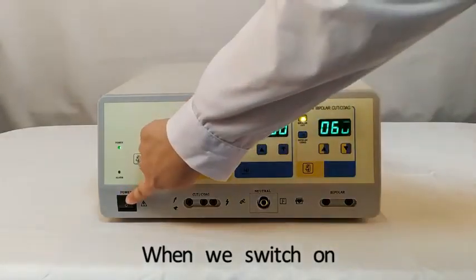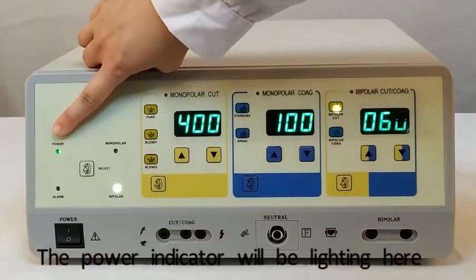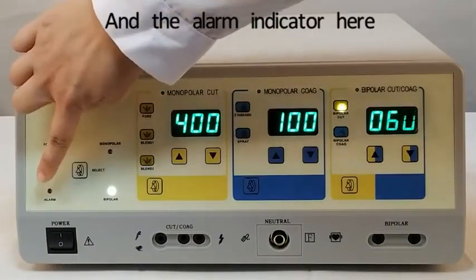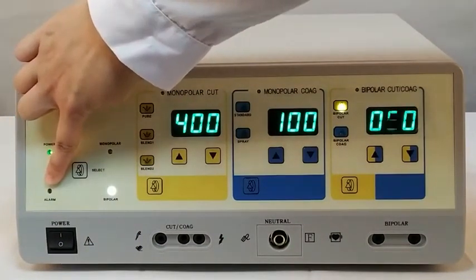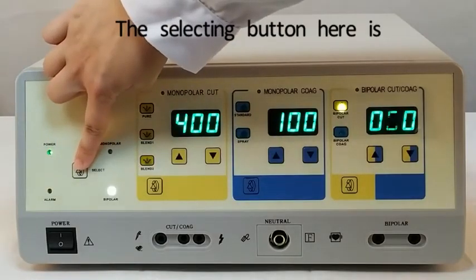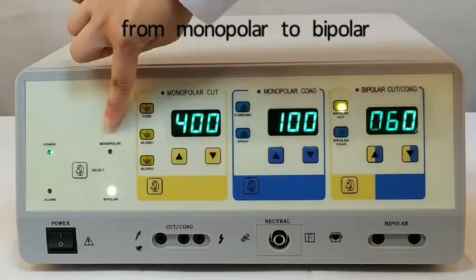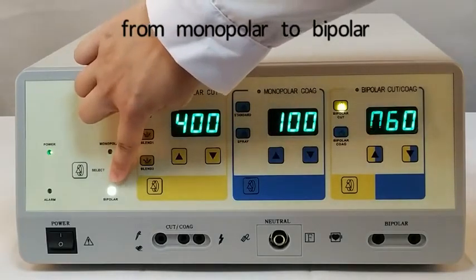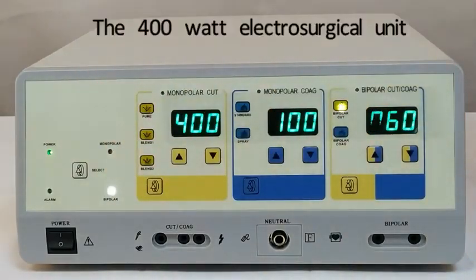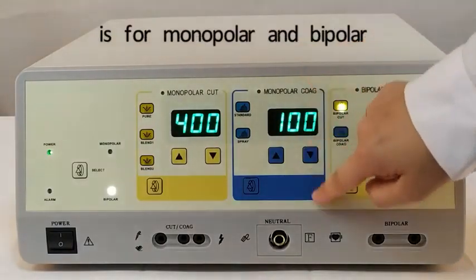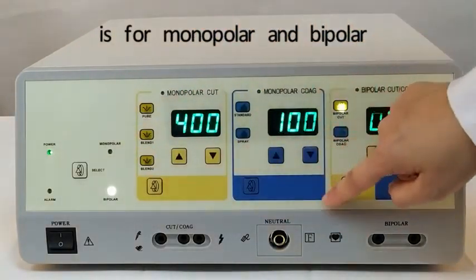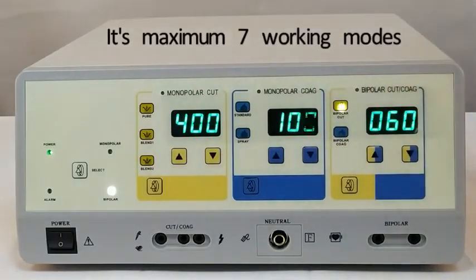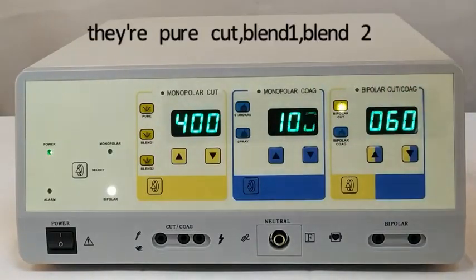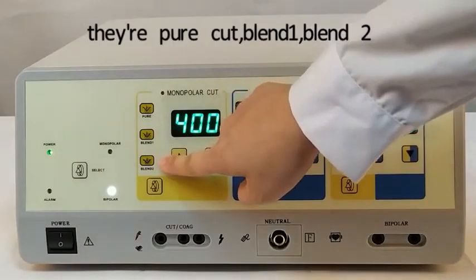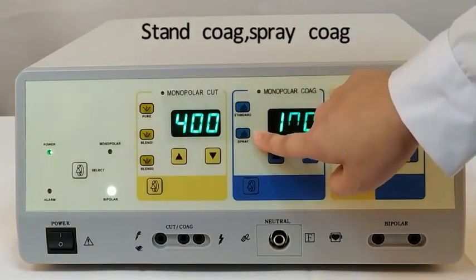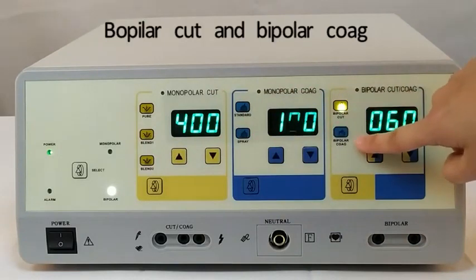When we switch on, the power indicator will be lighting here, and the alarm indicator here. The selecting button here is for changing the different working modes from monopolar to bipolar. The 400 watt electrosurgical unit is for monopolar and bipolar. It has a maximum of 7 working modes. They are pure cut, blend 1, blend 2, standard coag, spray coag, bipolar cut, and bipolar coag.